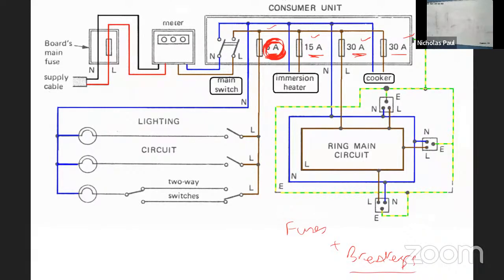For example, these 3 bulbs in parallel only take in a little less than 5 ampere current. This immersion heater is taking around 15 amperes. Your main ring is taking about 30, and the cooker is taking about 30. So if you go to your breaker panel, what you will see is 30 ampere breakers, 20 ampere breakers. For AC units, you might see 20 and 50.